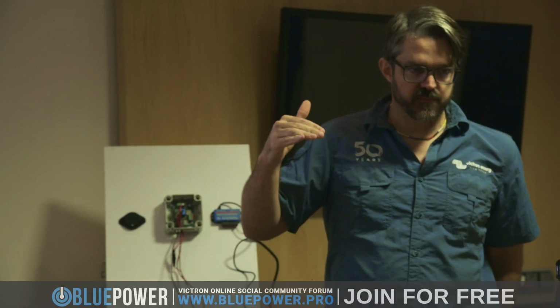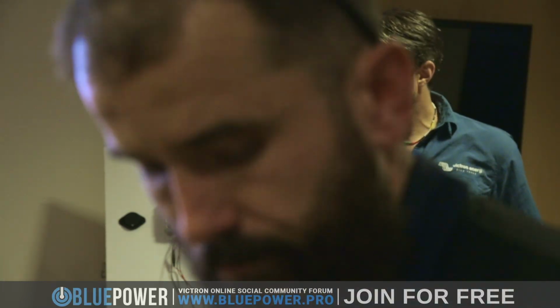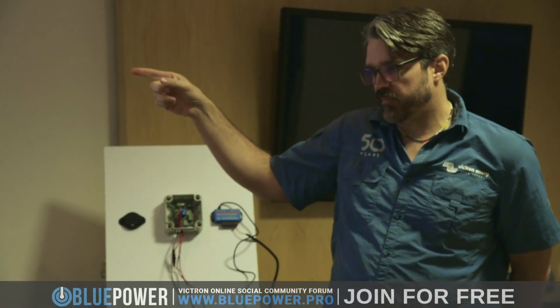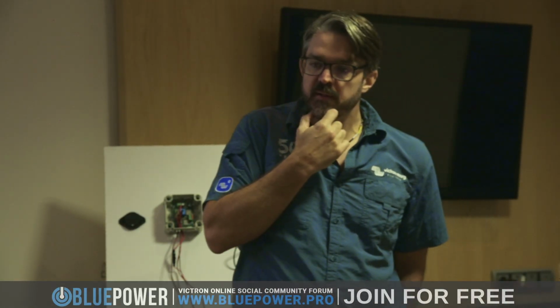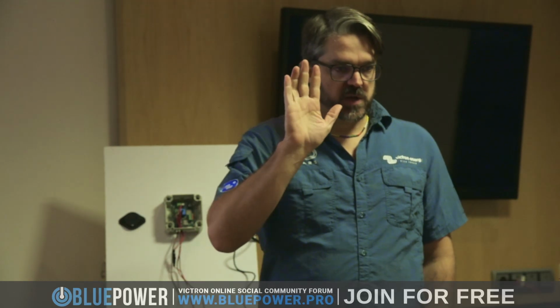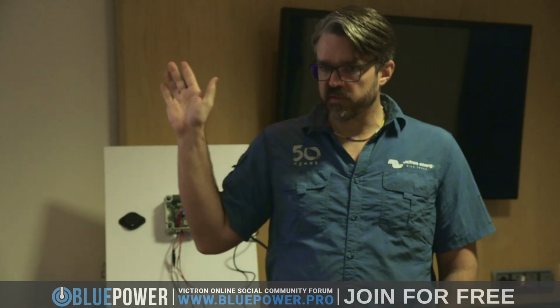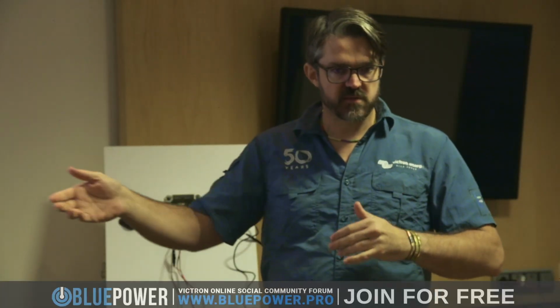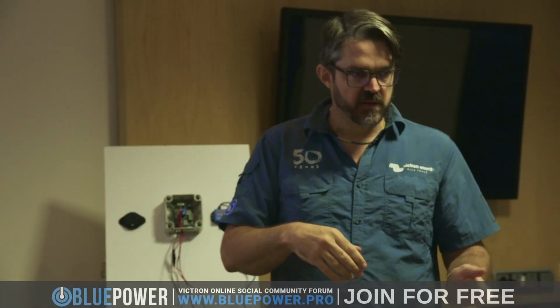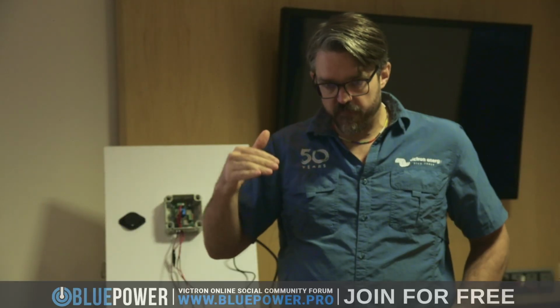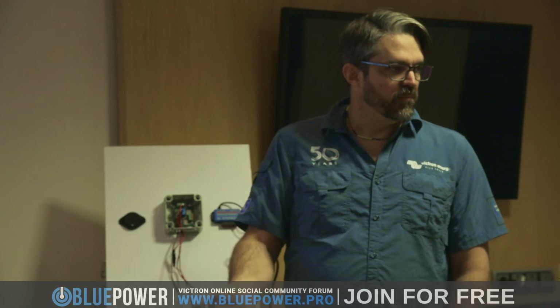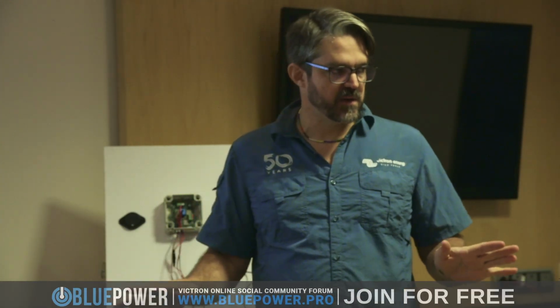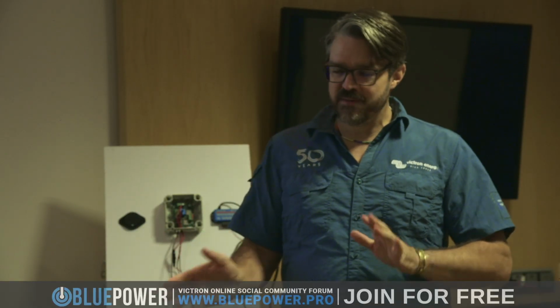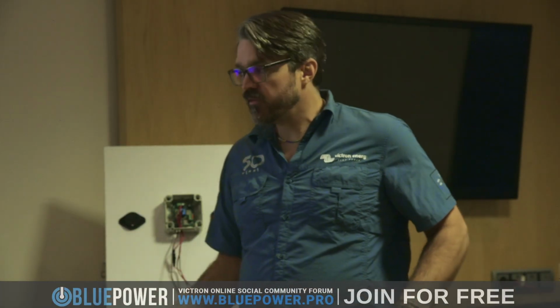Now you can also use Dynamic ESS when you have time of use tariffs, because they have a mode called fixed, which I think, Andre, are you going to show that? Yeah, exactly. I have a site where it's set up. Okay. So with fixed, you will have a schedule that comes from Eskom or from the city of Cape Town or whatever that tells you between this time and this time, this is the tariff in and out. And in fixed, you can basically build up that tariff model, and then it will buy power during the cheap time and sell it during the expensive time. That's Dynamic ESS. That's all it is. Buy when it's cheap, sell when it's expensive.